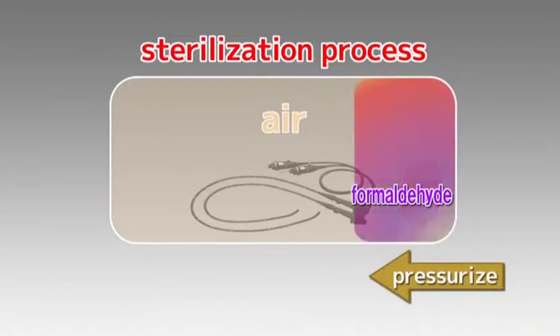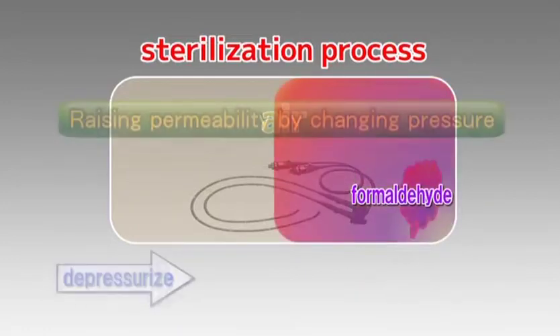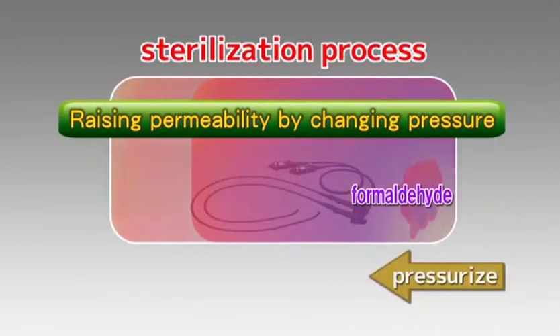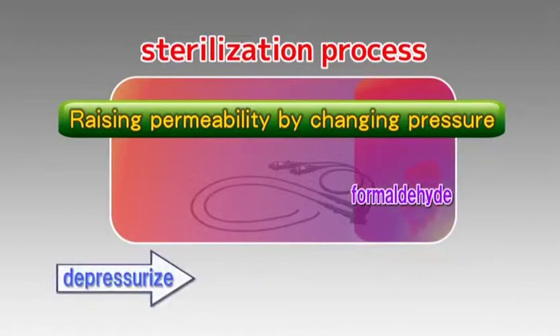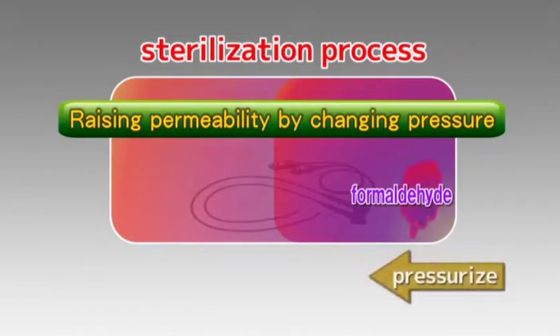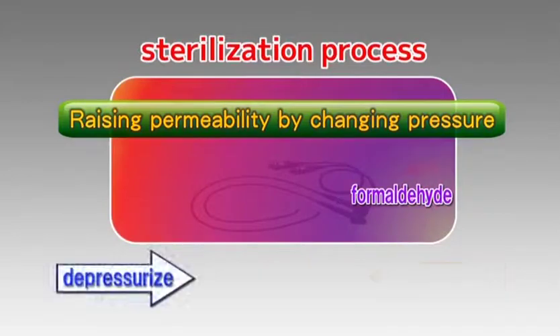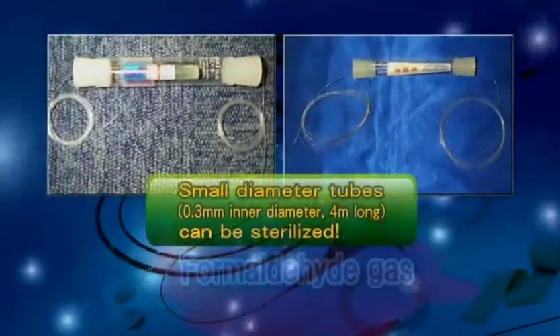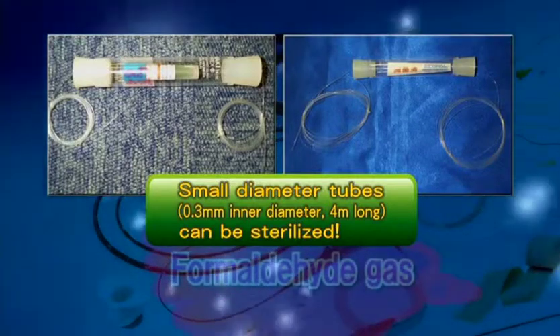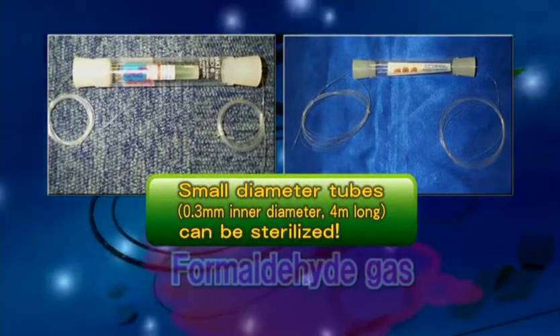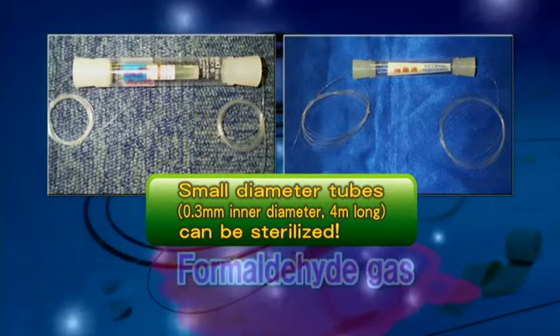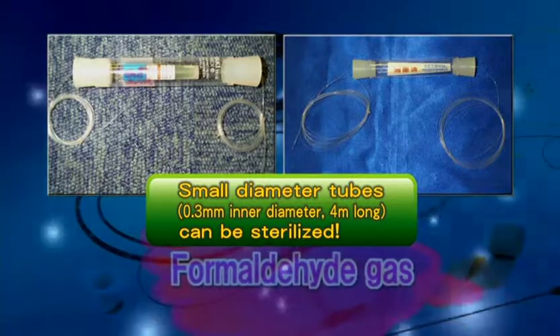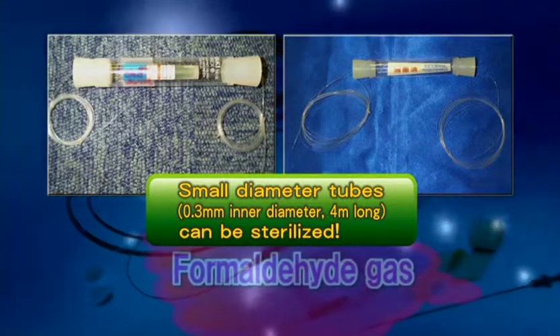We have succeeded in raising permeability substantially by repeatedly changing pressure in negative pressure condition, so there is no risk of a gas leak. Small diameter tubes can be sterilized with our new device. Tubes with a minimum inner diameter of 0.3 millimeters up to 4 meters in length can now be sterilized.